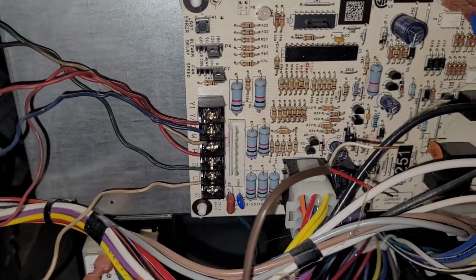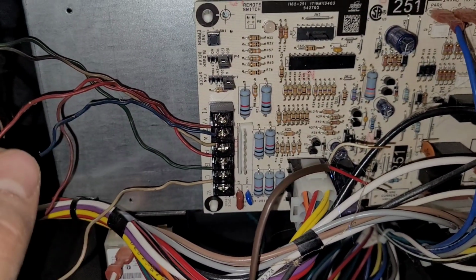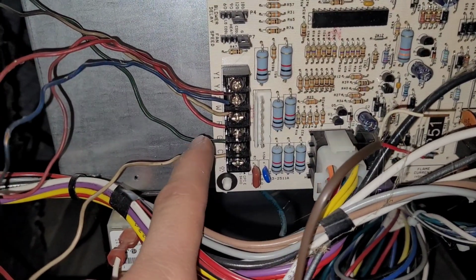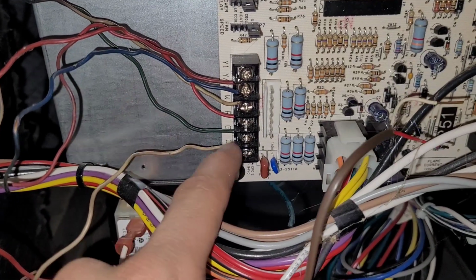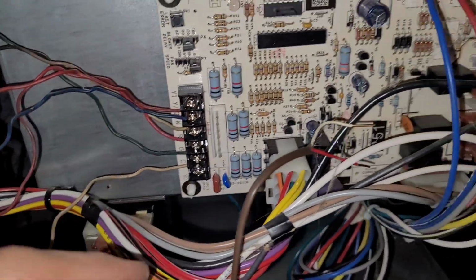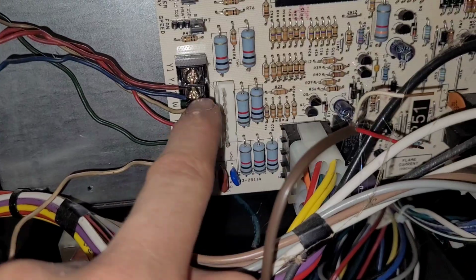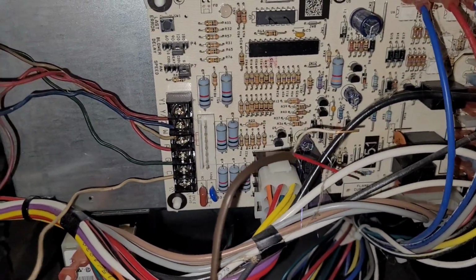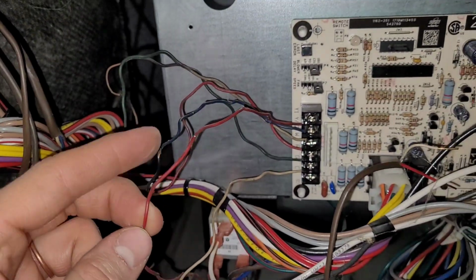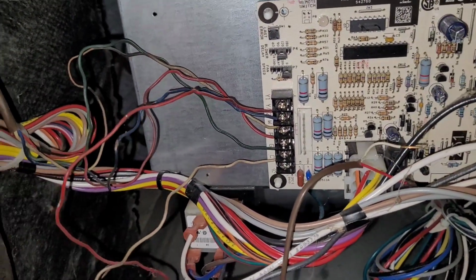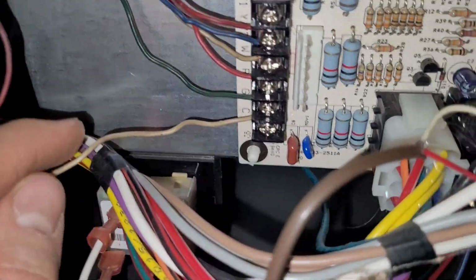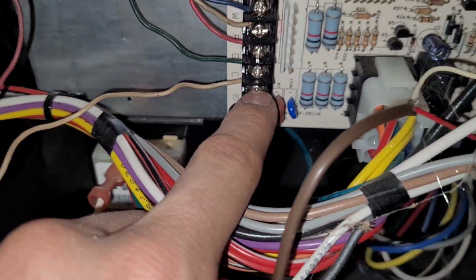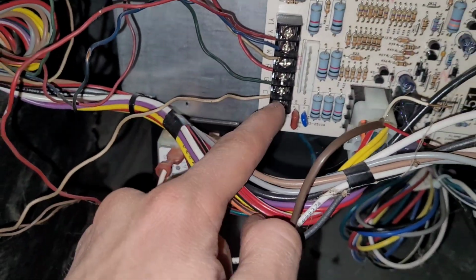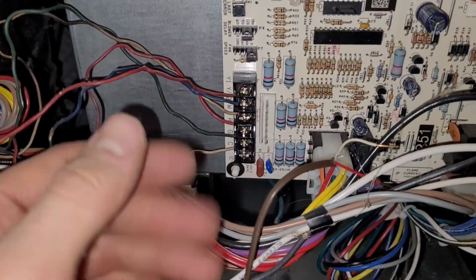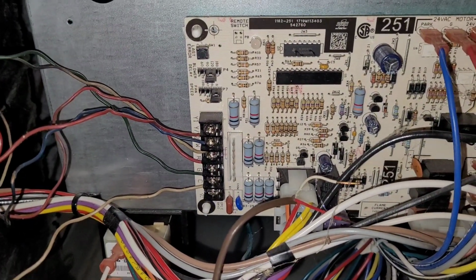If you want to run just the fan, then you switch that fan switch on the thermostat, and it sends the voltage down on this G wire, which brings on the blower. If it wants to bring on air conditioning, then it just sends that 24 volts down on the Y. And there's a second wire, this red one right here. This actually goes out to the air conditioner and brings on the contactor, and the other wire for the air conditioner contactor is just hooked directly to the C. I don't have 5 wires, so I don't have a C wire coming from my thermostat, so I have to use batteries in my thermostat, but that's fine.